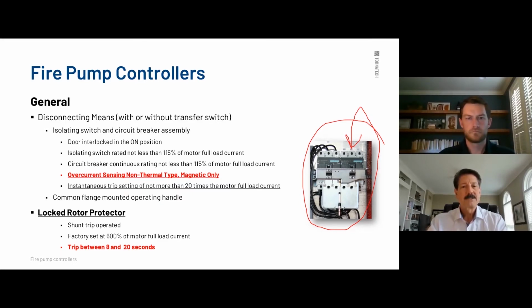Again, this is standard equipment for everyone and not specific to Tornatech, but this is how we mount side by side. As you'll note, both breakers have a common faceplate with the operating device coming up the middle. And what that does is allow equal force to be distributed across both toggle switches of the circuit breaker itself. And it makes it much easier because it's uniform. You don't have a side-mounted device where you're actually operating a spring device across both with a pivot point, because sometimes over time that spring can actually weaken.